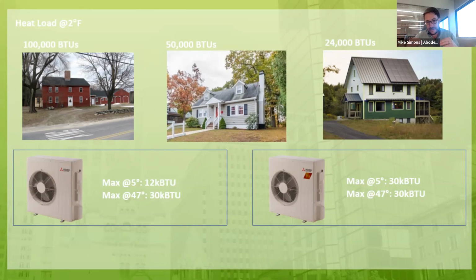So let's now look at the bottom of the slide. On the bottom of the slide, I have two different types of heat pumps. One is a traditional heat pump and one is a cold climate heat pump. The difference between the two is, if we look at the performance of a traditional heat pump at 47 degrees outside, that heat pump can introduce 30,000 BTUs per hour to the home. But at 5 degrees, that heat pump can only put out 12,000 BTUs per hour.